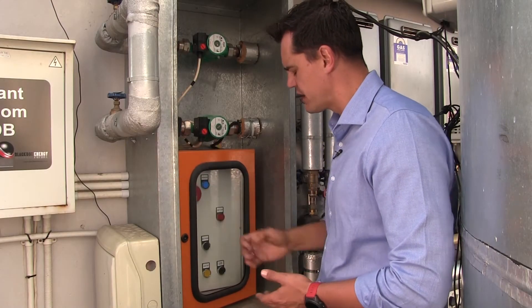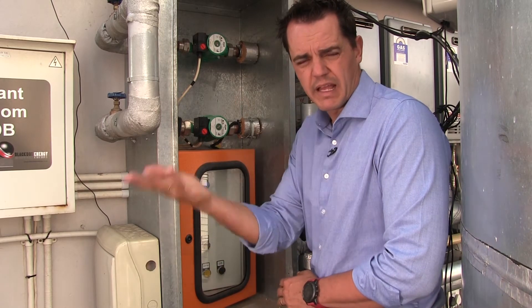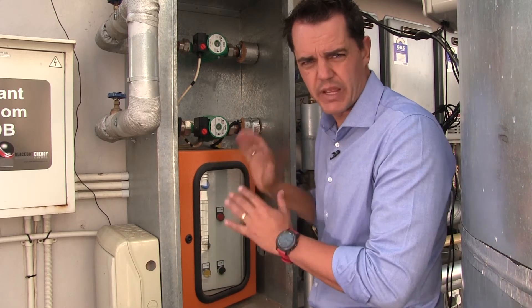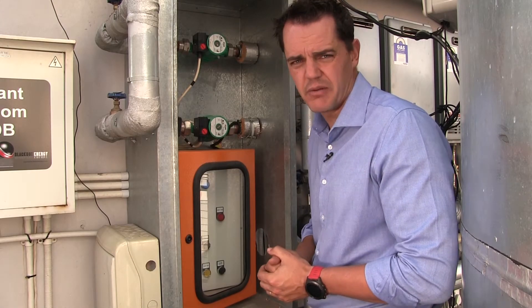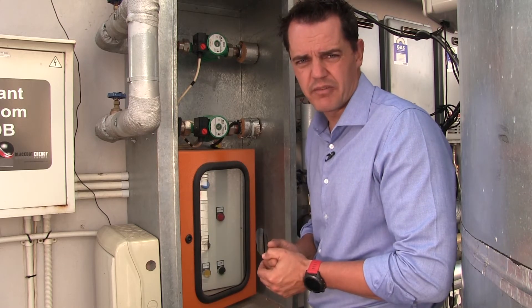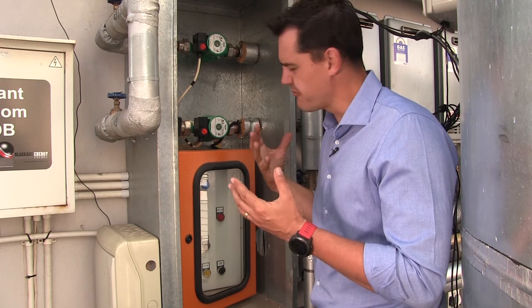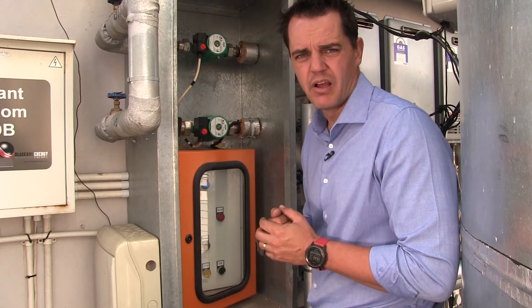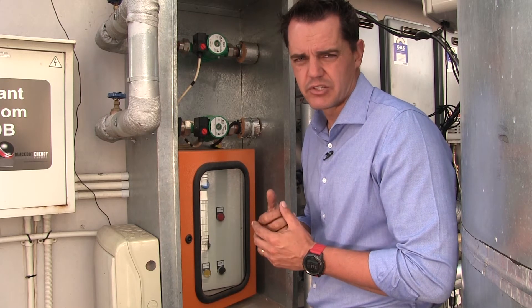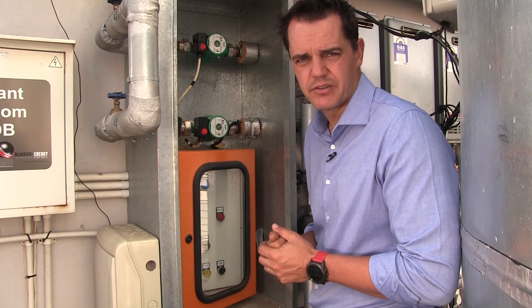In summary for the ring main circulation: check flow, check temperature. If there's hot water in the tank but no hot water in the building, this is where your failure point will be in terms of ring main circulation. Thank you for watching this video. Also watch our other videos which will give you a more advanced understanding of identifying and operating this David Webster hot water system, based on solar and gas heating, to ensure continuous and excellent service delivery for our students. Thank you.